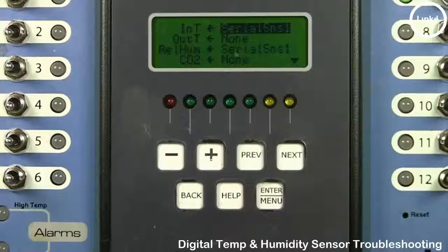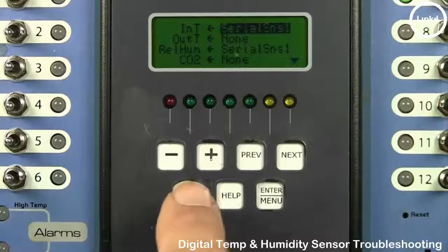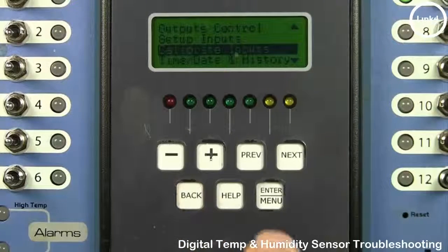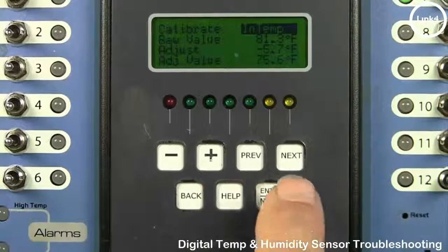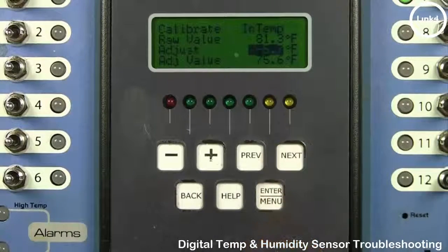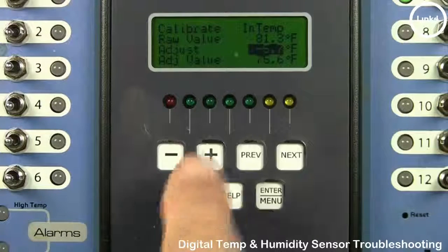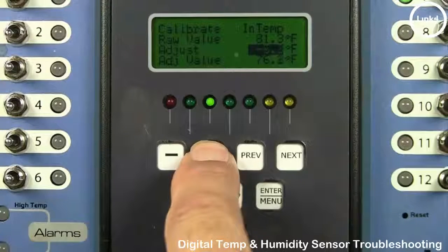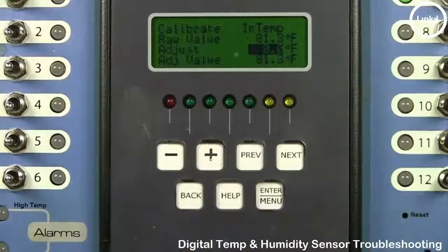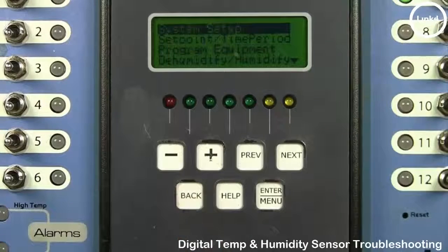And as you can see, the in-temp is Serial Sensor 1, and the relative humidity as well is Serial Sensor 1, so this sensor is in fact mapped correctly. Hit Back. Also go into Calibrate Inputs to make sure that no values in the adjust row have been inputted to change the adjust value. Now, the raw value is the actual sensor reading and the adjust value is the offset of the adjust. But what we're going to do is make this real fast be zero so that the adjust value and the raw value are the same. Hit back till you get to the home screen.